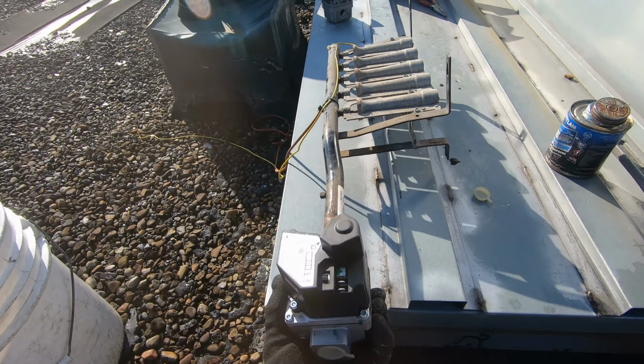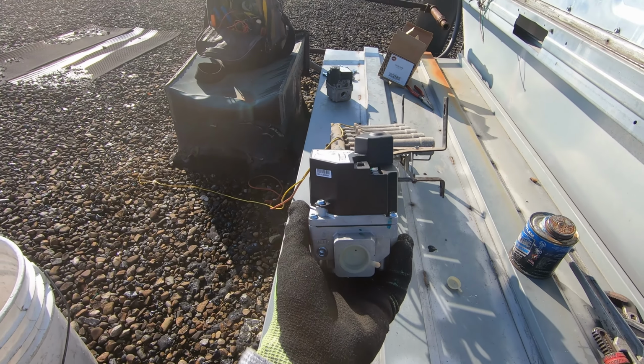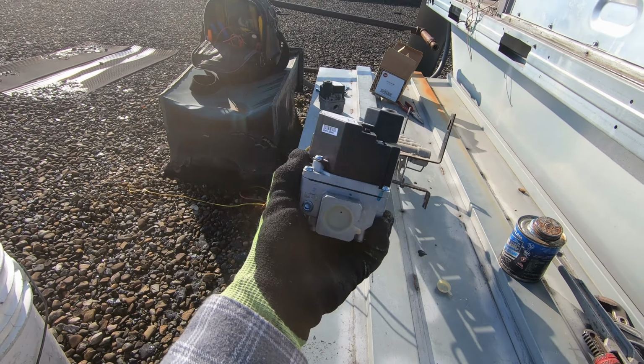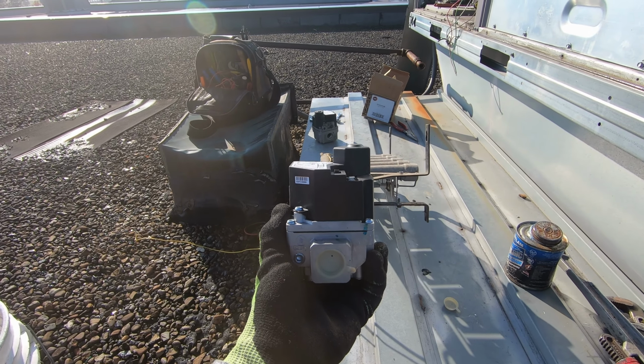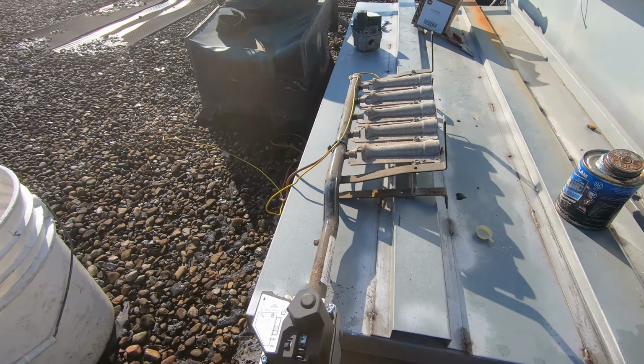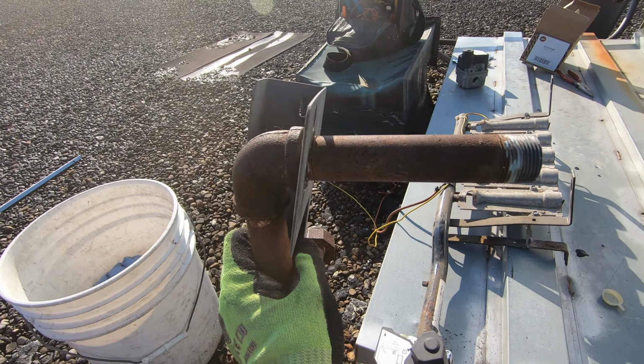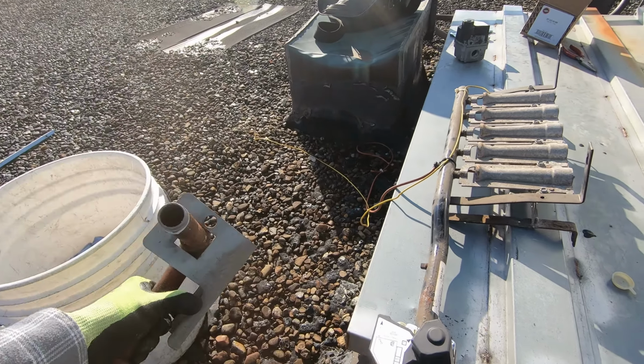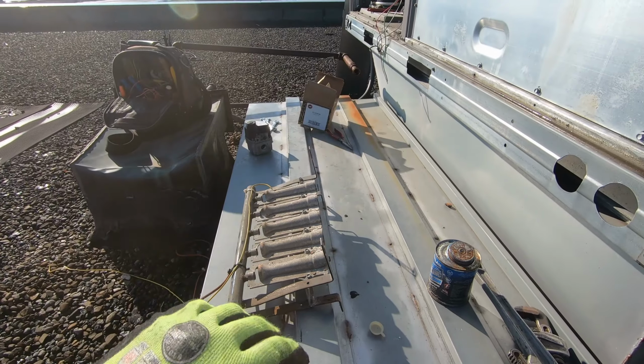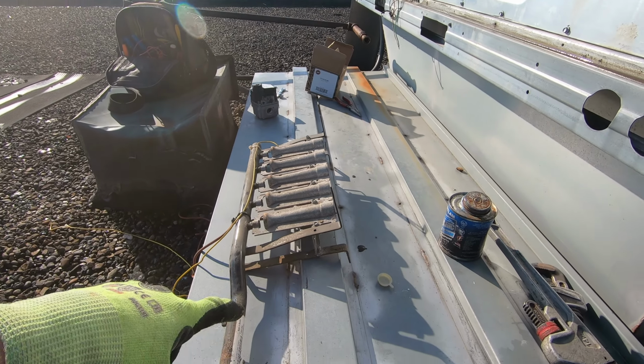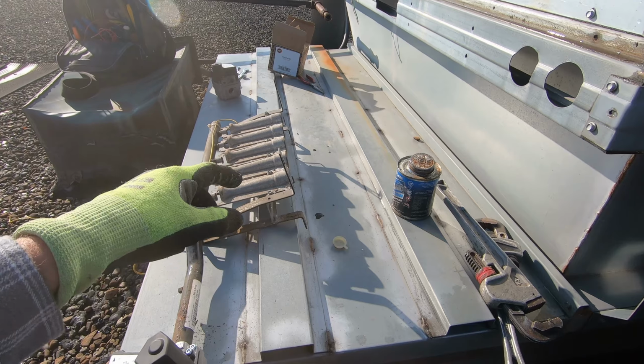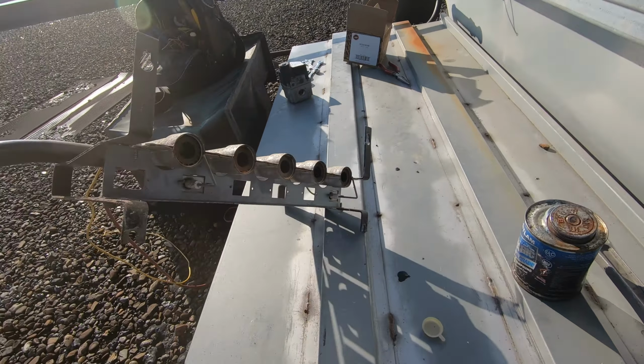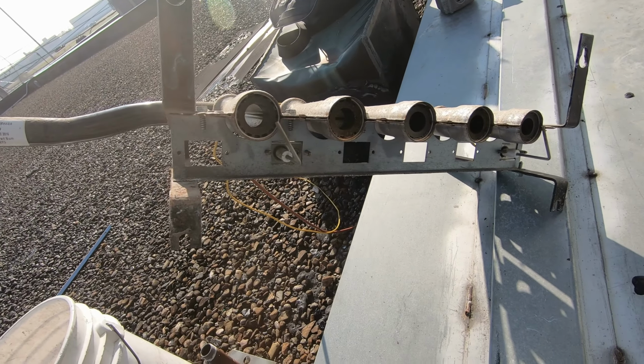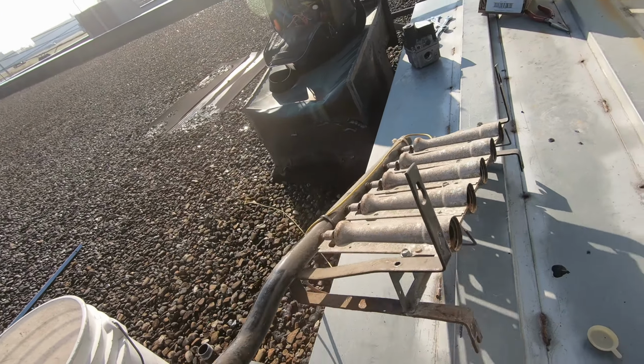Alright guys, I've got the gas valve in line, level with the burners, and I'm gonna put this in last. Once I get the mounting bracket put in place, I'll pipe that in place with this in. What I'm gonna do now is just go over these burners, go over this flame sensor and igniter with a wire wheel and a wire brush, clean them up, and we're gonna stick it back in.